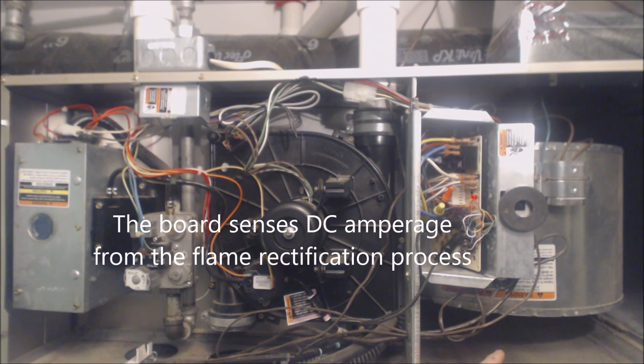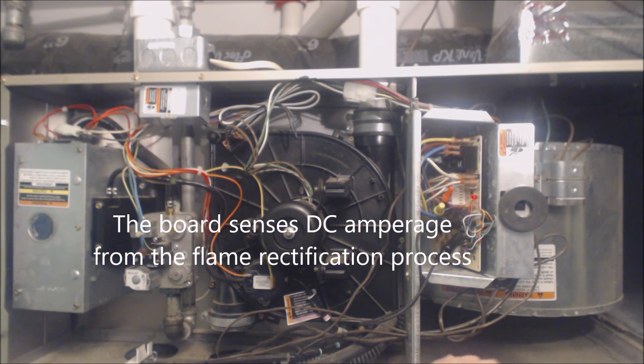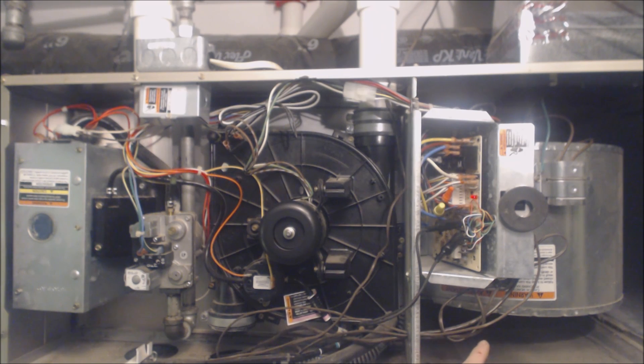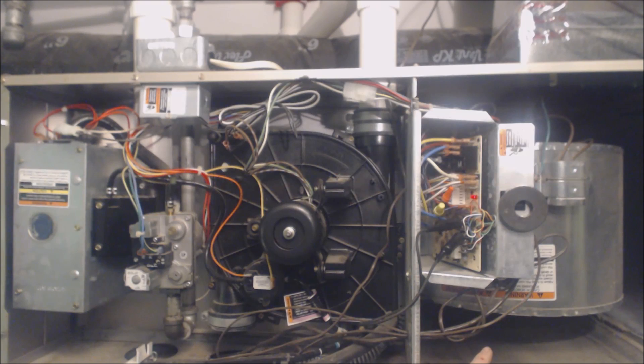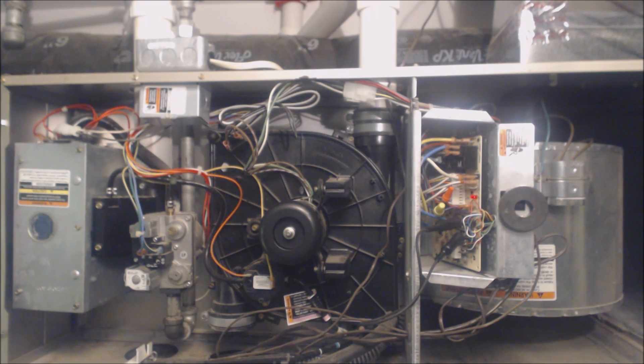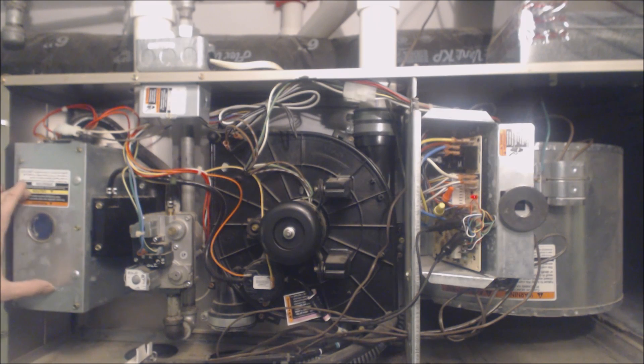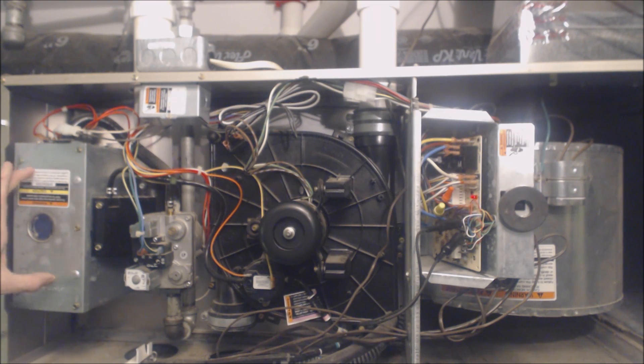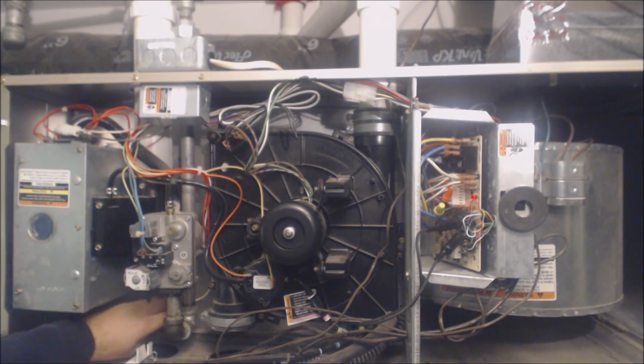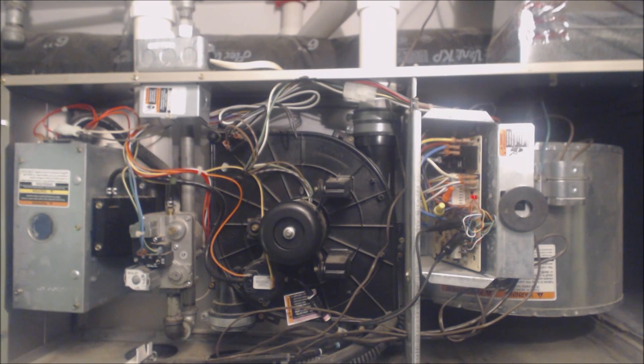What you have is a 20 second on delay before the blower motor turns on. The blower motor just turned on just now. After the blower motor on delay of 20 seconds, the blower motor turns on. What it was doing while the flame was running before the blower motor turns on is heating up the heat exchanger so you don't have cold air blowing on the homeowner.